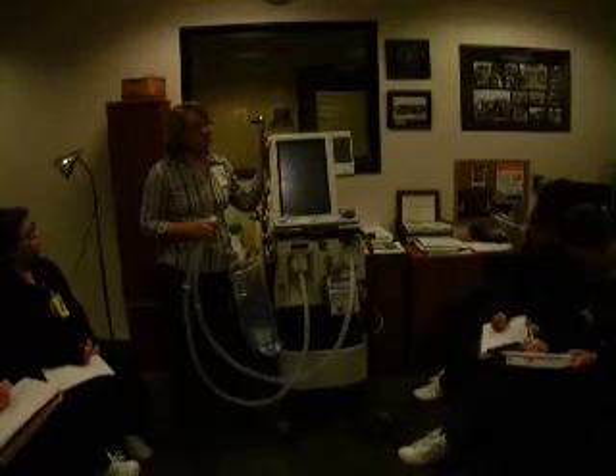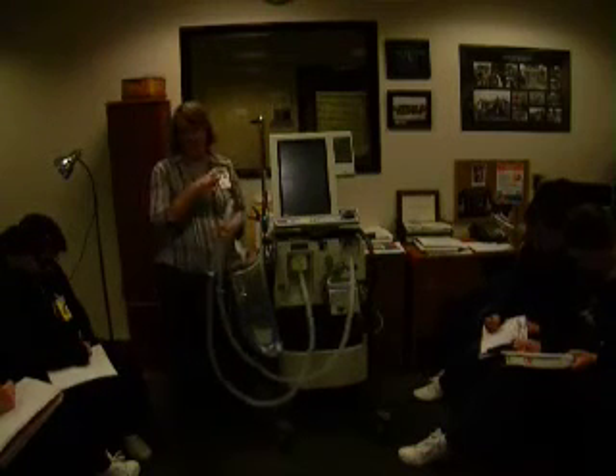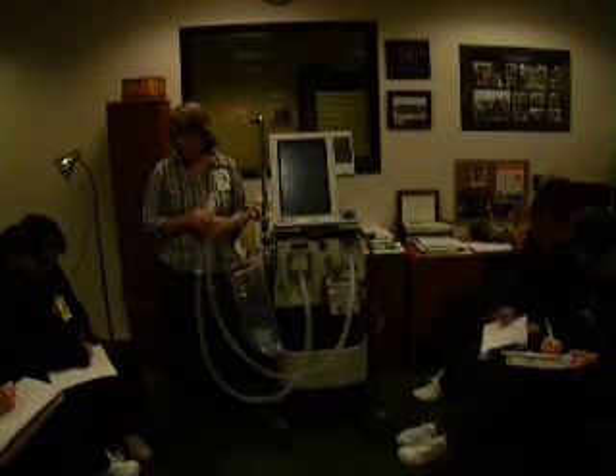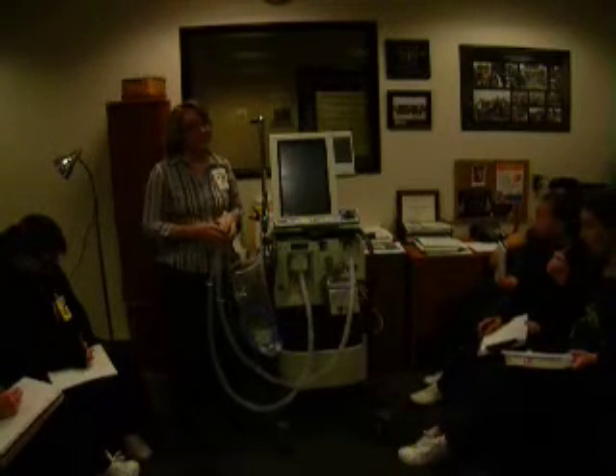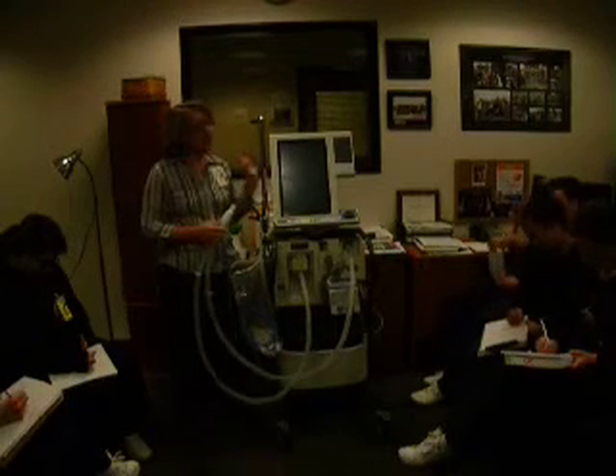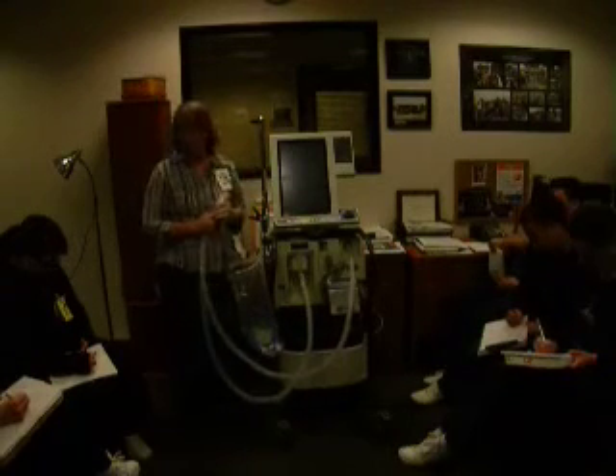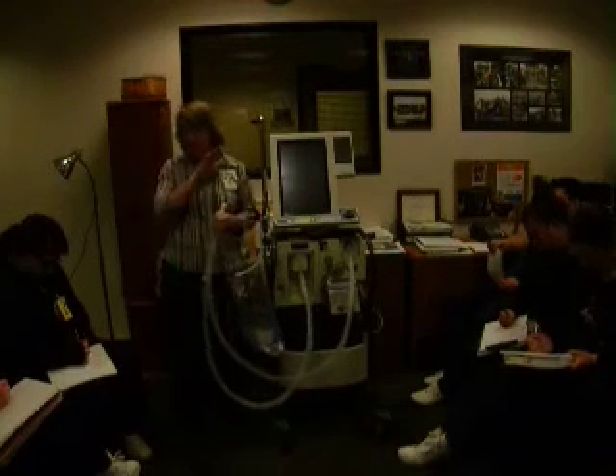So when I did that, it went into safety ventilation. Safety ventilation, and there's safety valves. The safety ventilation on this ventilator sets its own kind of little, okay, I'm in safety ventilation. I have these preset settings I'm going to deliver to the patient. There's also safety valves in the ventilators. Every ventilator has a safety valve, and it's one of the most important features because a safety valve is a valve that will open up and allow the patient to get room air.